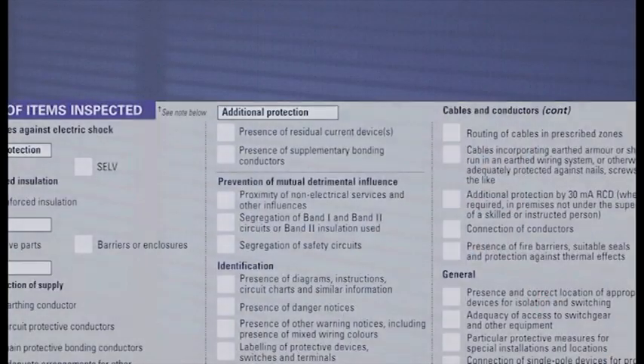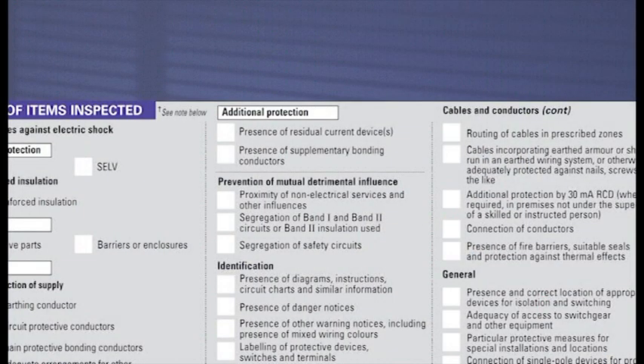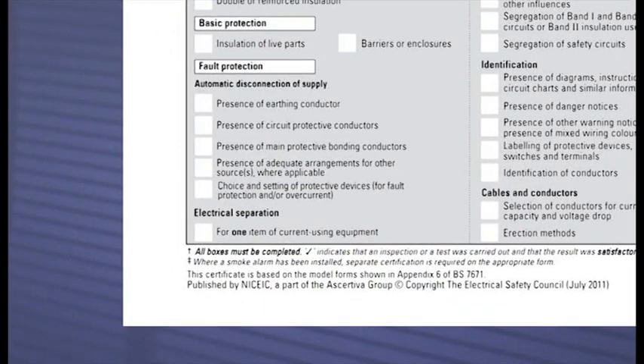For example, a 300 mA RCD which may be provided for fire protection would not result in a tick in the box presence of residual current devices under the subheading of additional protection. This instead would fall for consideration under the box choice and setting of protective devices.